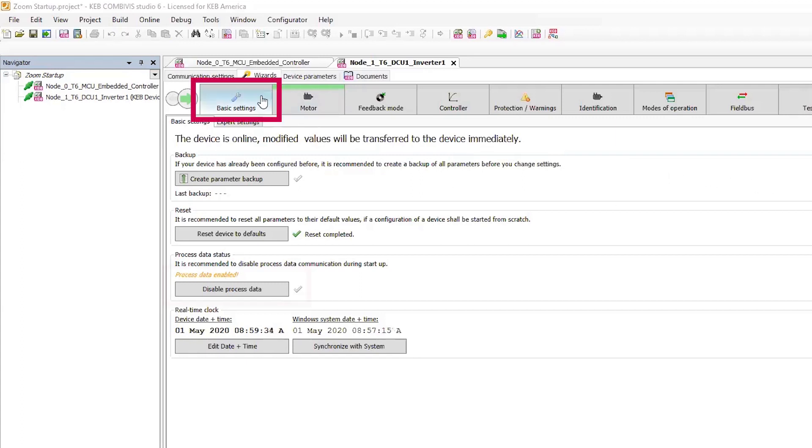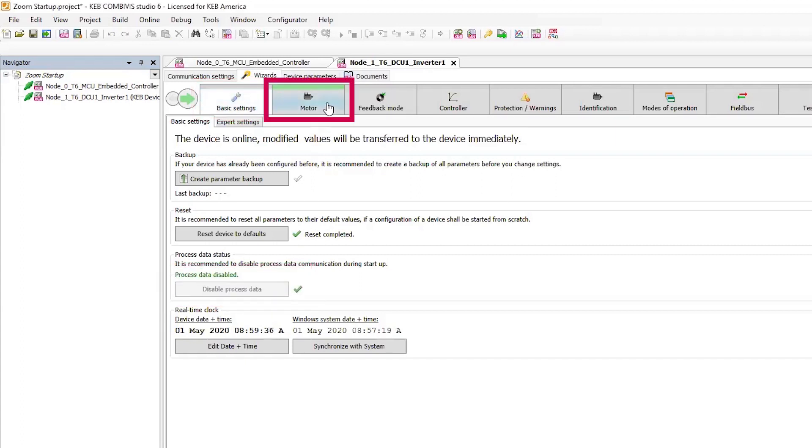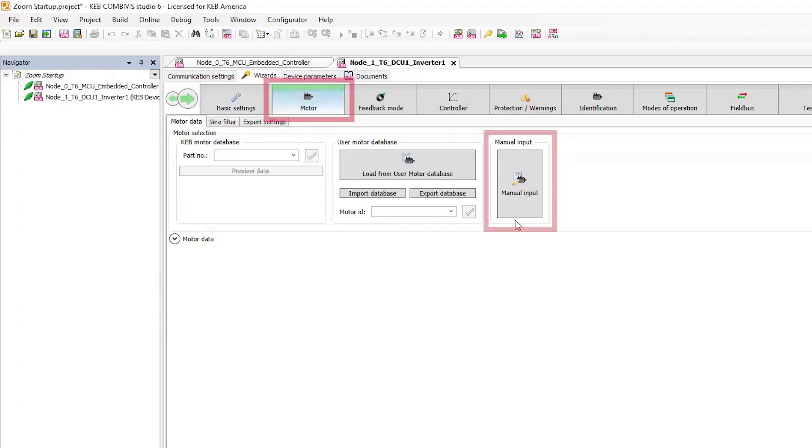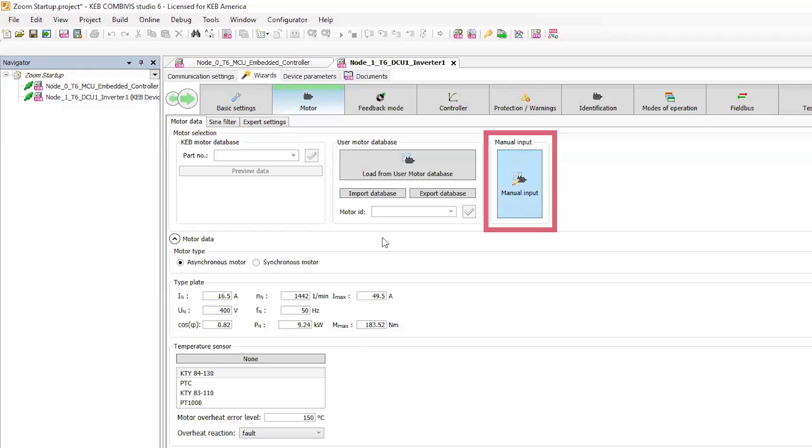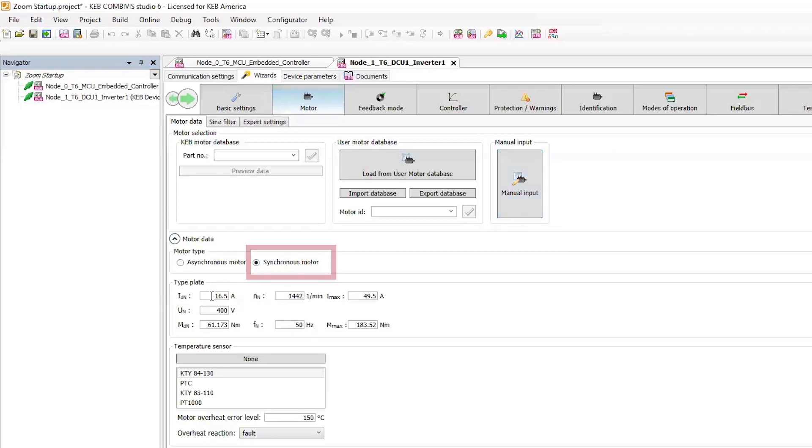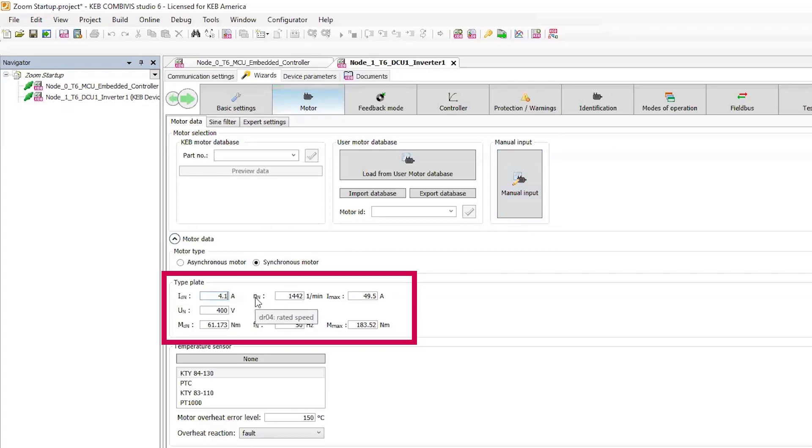Starting in the basic settings tab, I'll disable the process data since I don't have the CAN set up. Then in the motor data tab, I'll select manual input, I'll select the motor type, and then enter in the basic motor nameplate data.